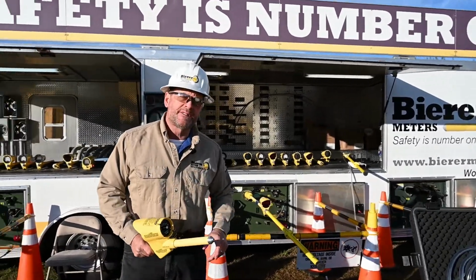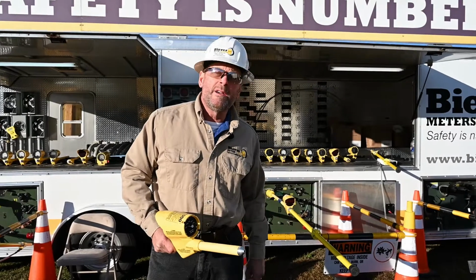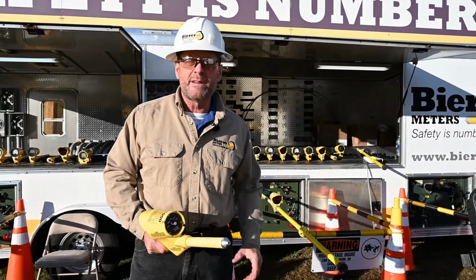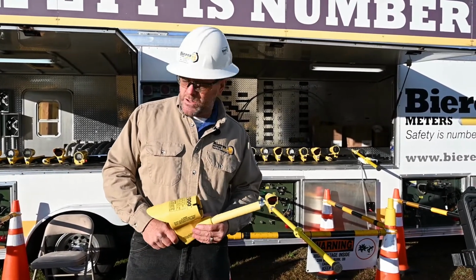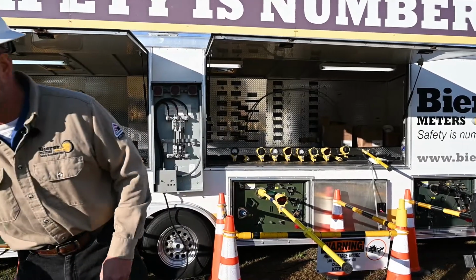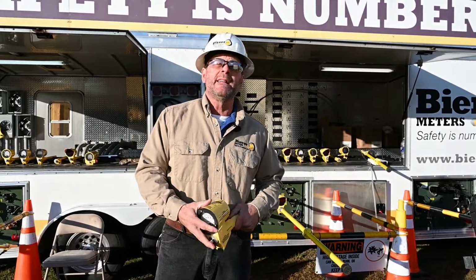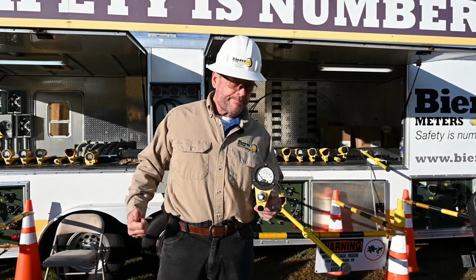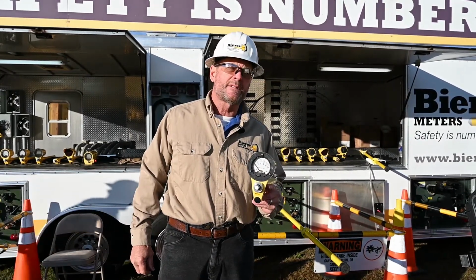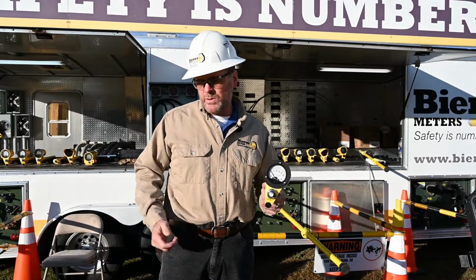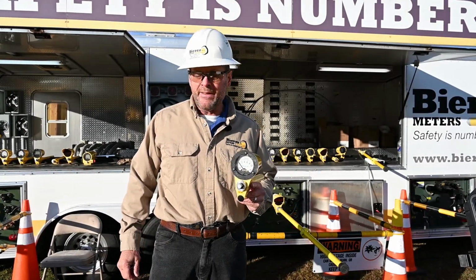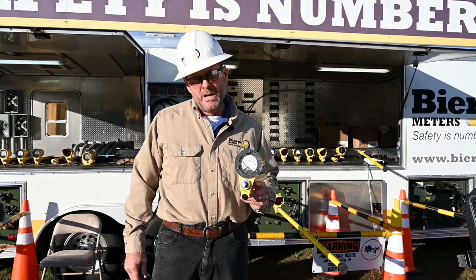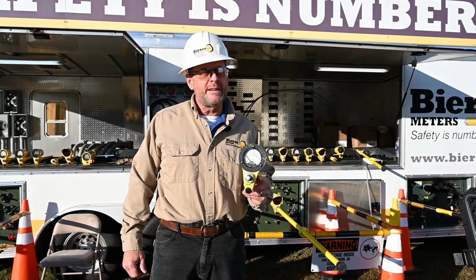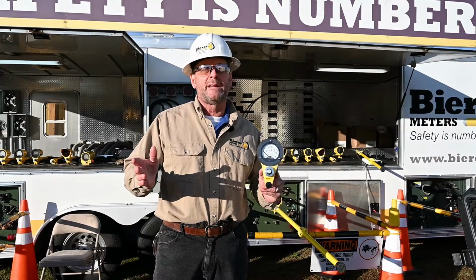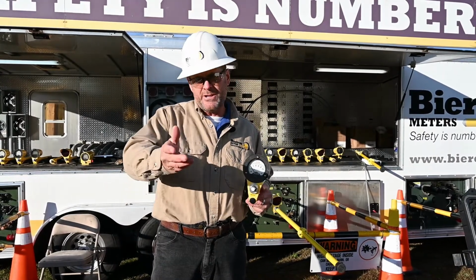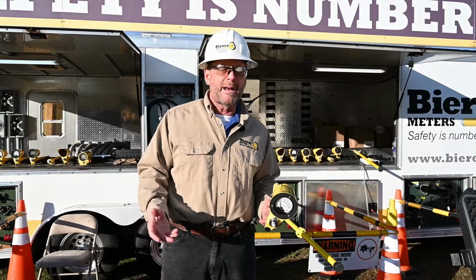So proper body position, we get a call from Illinois, and the lead lineman said your analog tool is no good, it sucks. He said he's getting 13,000 volts on 7200. They've had the tools for 5-6 years, and now the lead lineman's getting inaccurate readings. He's on 7200 and getting 13,000 volts, and automatically I know what's going on, and you guys should know too. He's got improper body position, period.